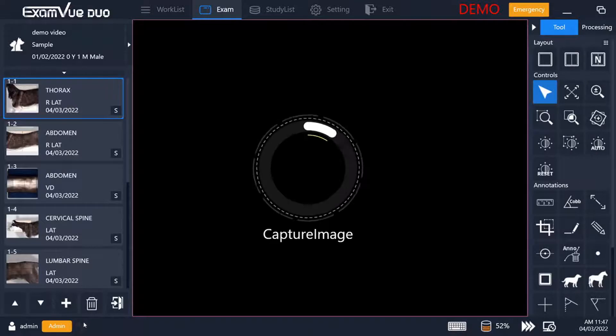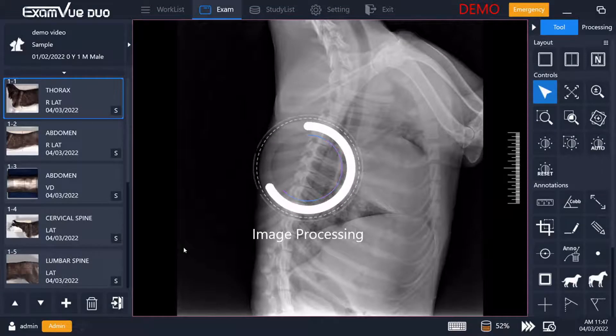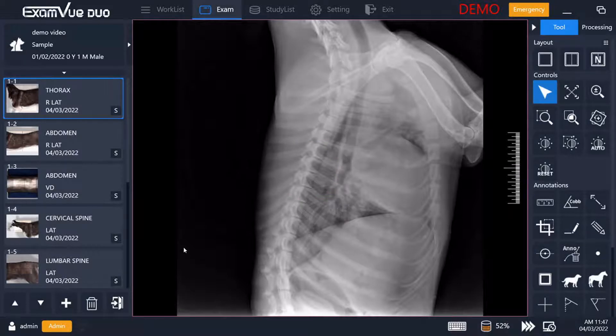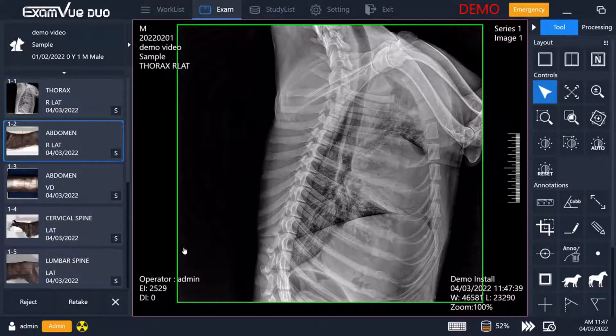Once you've clicked exam, it will connect to your detector and will be waiting for your detector to present the images. You do not need to select anything for it to detect when you've taken an X-ray. If everything goes correctly, you could from this point forward not touch the software again. When you take the X-ray it will automatically display it to you for review and move on to the next X-ray. You will see it give you the option to reject or keep this X-ray, or you can simply ignore this and move on without needing to redo it.